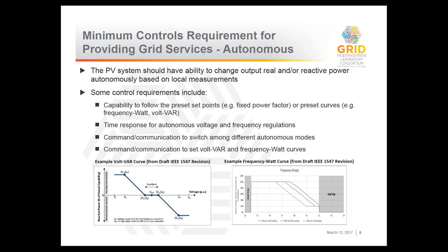For example, these are some sample curves, just to give you an example if you're not familiar. The lower left one shows the volt-var curve. Basically, you are measuring the voltage at the terminal of your device or some other remote point, and based on that voltage, you are injecting or absorbing reactive power to mitigate the voltage issue. The other one shows the frequency-watt curve, where you are changing the output of your inverter to support the grid when there is a frequency issue, when the frequency is beyond the normal operating range. Again, these are example curves. This in no way represents every possible way of doing those curves, but it gives you some idea of how they will look.